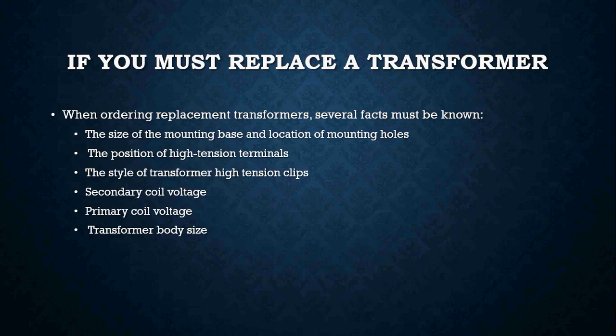So if you must replace a transformer on an oil burner, you have to make sure that you know a couple of the facts that go along with them. First off, you have to know the size of the mounting base and the location of the mounting holes. You have to know the position of the high tension terminals, the style of the transformer, high tension clips, if there are any. You need to know the secondary voltage. You need to know the primary voltage. And you also need to know the type of transformer body.